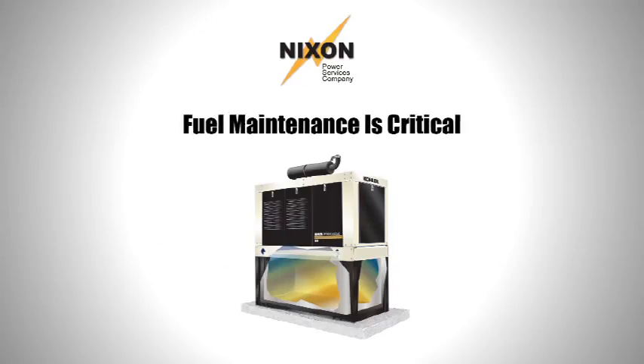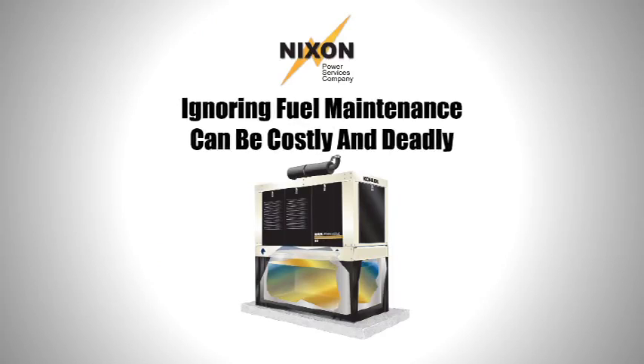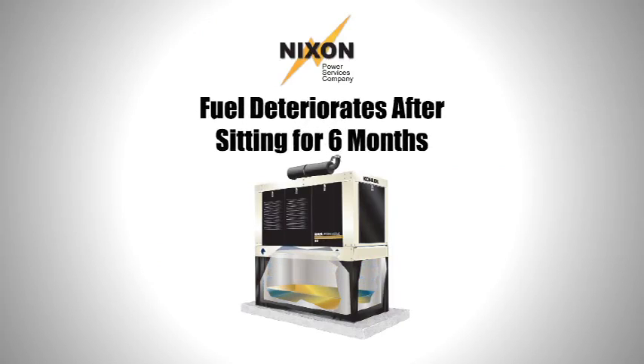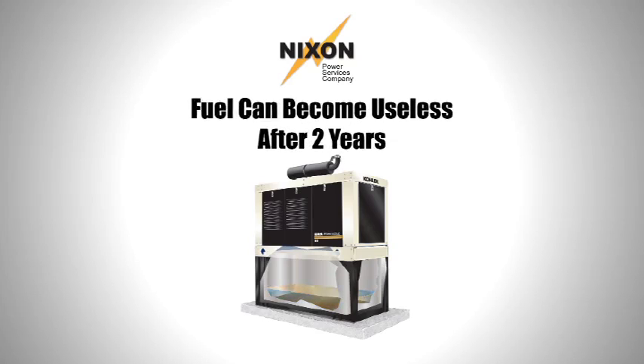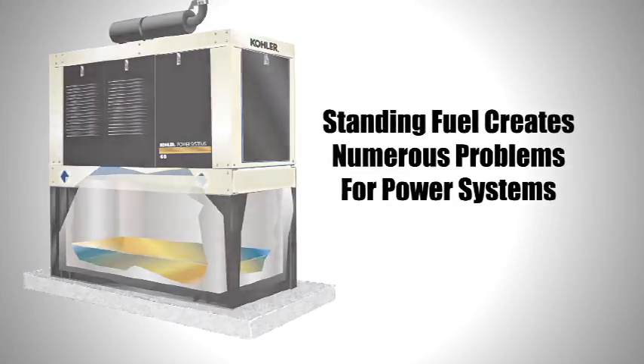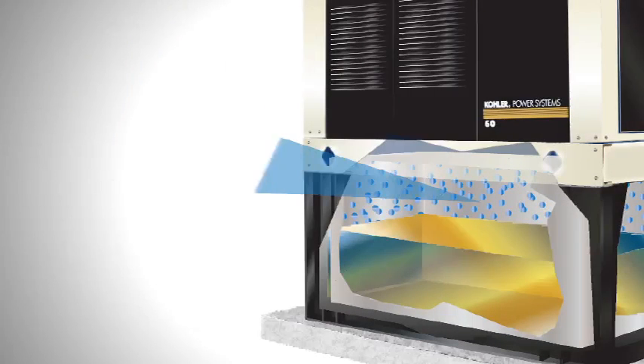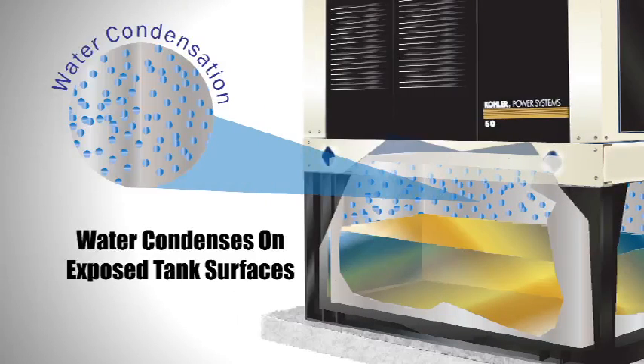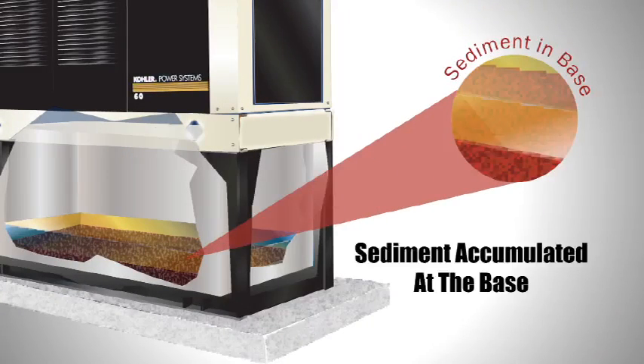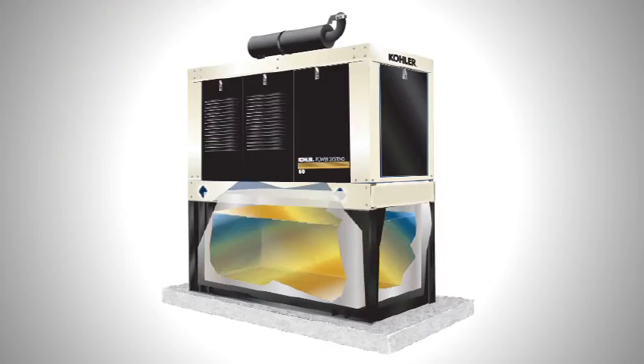One of the most common causes of failure and reduction in performance is insufficient attention paid to a system's diesel supply. Diesel left standing for extended periods degrades substantially to the point of becoming totally useless. Standby power systems are particularly susceptible to diesel fuel issues because their fuel source is left standing for several months. Diesel is particularly susceptible to degradation by water, which further degrades the fuel and increases sediment accumulation in the base that can be sucked into the engine's fuel delivery system. If nothing else, a diesel tank should be kept full.